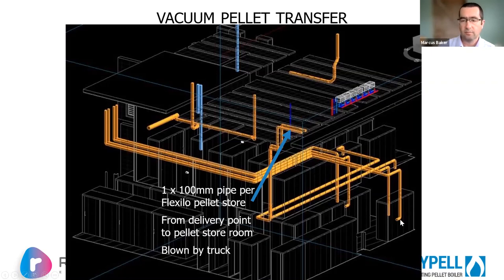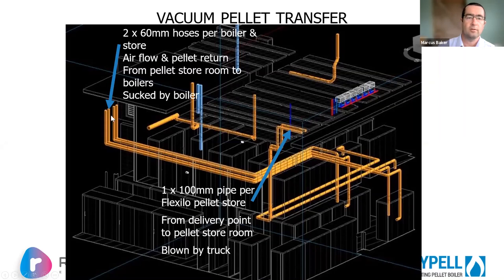And then from the Flexilos, we've got a flow and return. So these are 60 millimeter plastic hoses with anti-static windings on them. And as you can see, they're going around a few corners and up and down. And they will have one with air being blown from the boiler. And then as it passes through the head of the pellet delivery system, pellets get dropped in and then they get blown back to the boiler.